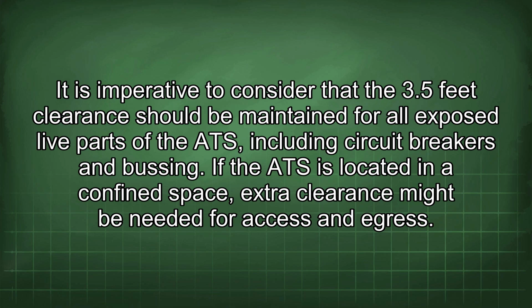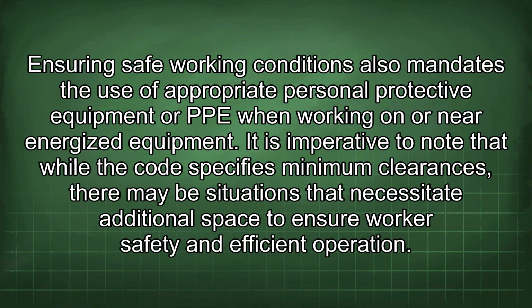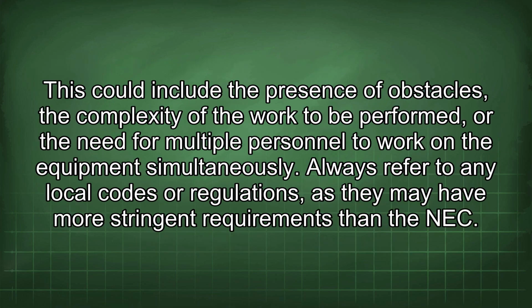If the ATS is located in a confined space, extra clearance might be needed for access and egress. Ensuring safe working conditions also mandates the use of appropriate personal protective equipment, or PPE, when working on or near energized equipment. It is imperative to note that while the code specifies minimum clearances, there may be situations that necessitate additional space to ensure worker safety and efficient operation. This could include the presence of obstacles, the complexity of the work to be performed, or the need for multiple personnel to work on the equipment simultaneously.